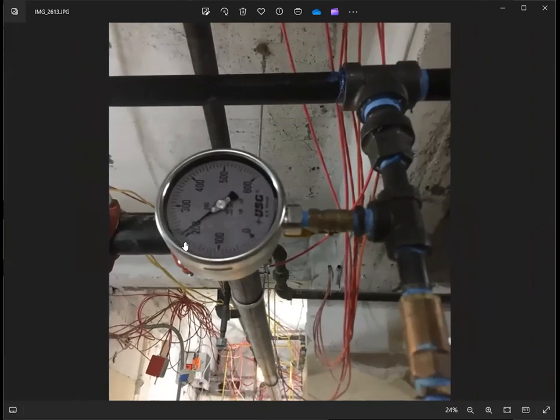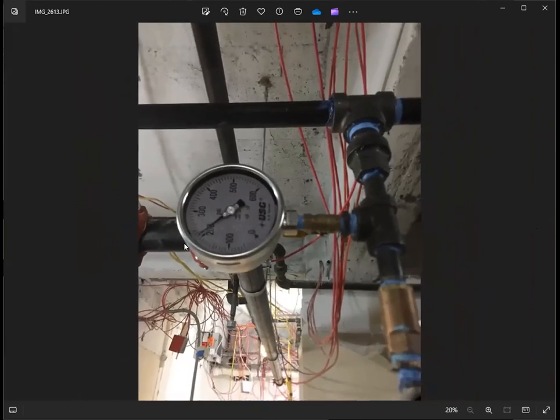So I think we are testing two systems here because I believe they have two stairs. This temp loop sprinkler assembly is only assembled and installed on the stairs. So if ever there's a fire condition on the job, the only sprinkler area is the egress or the exit path for the workers.